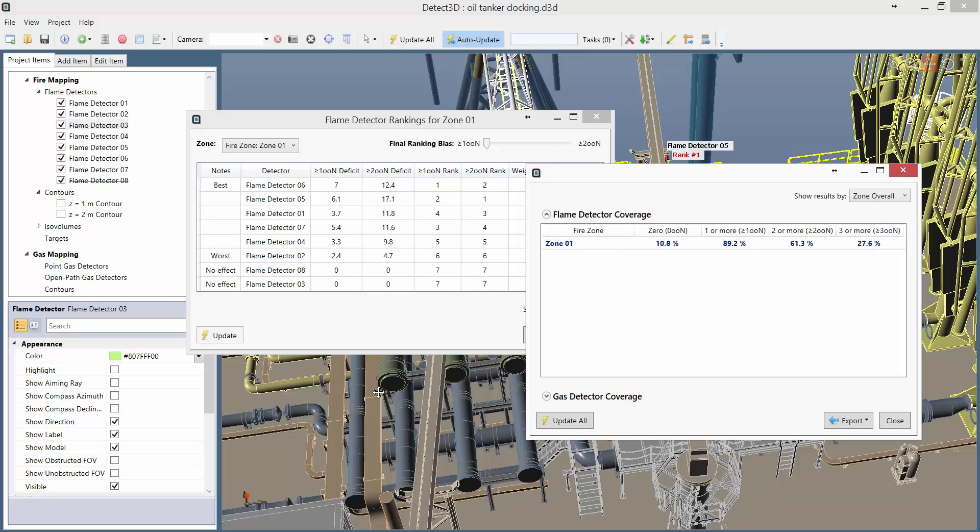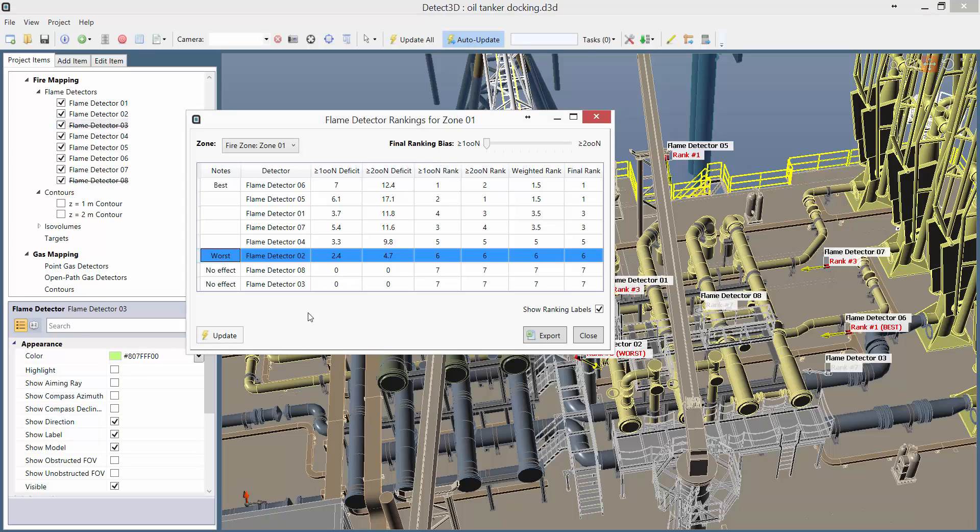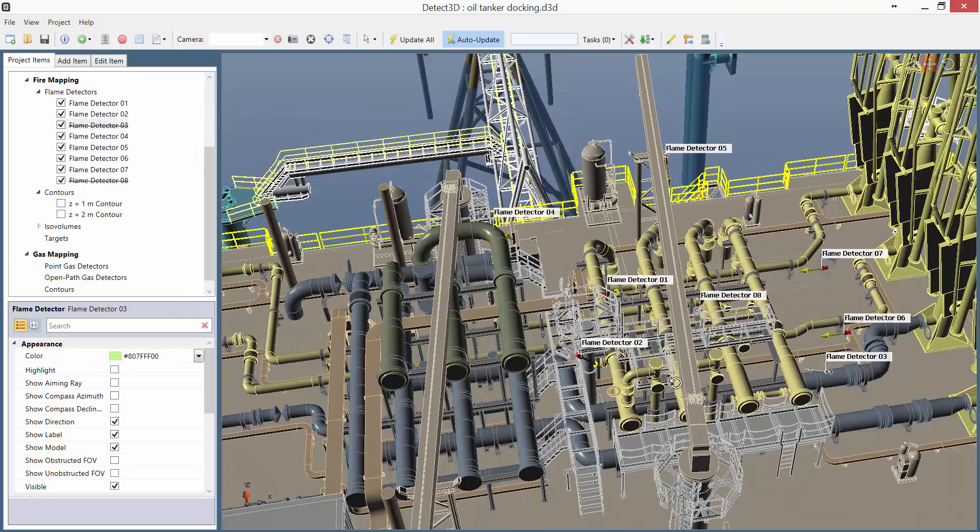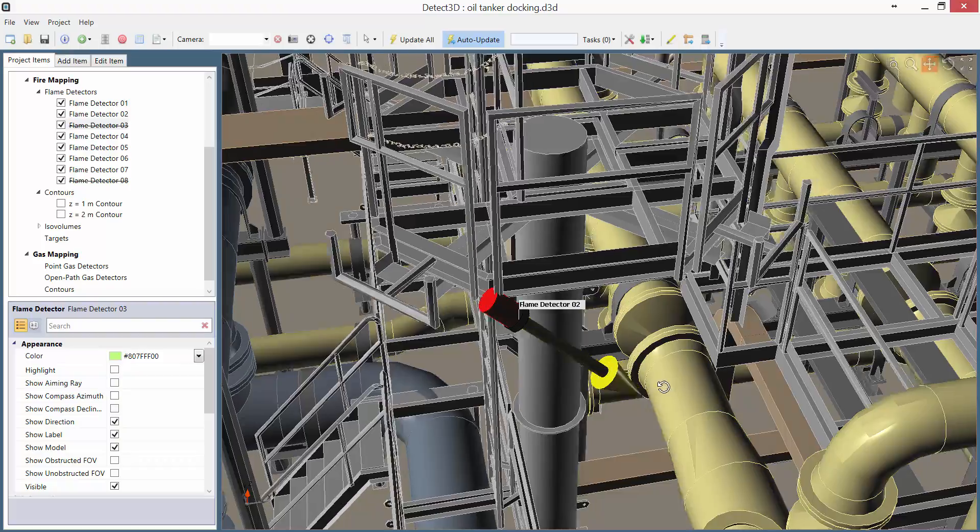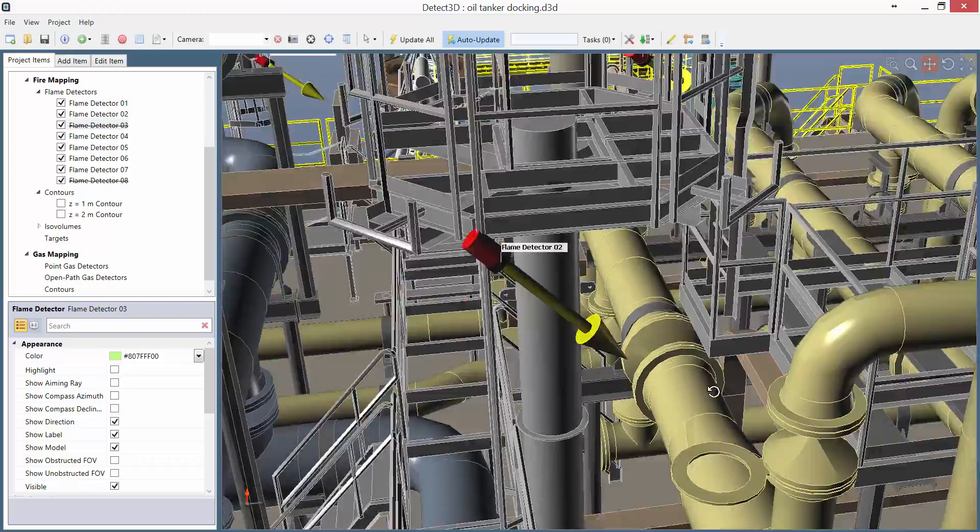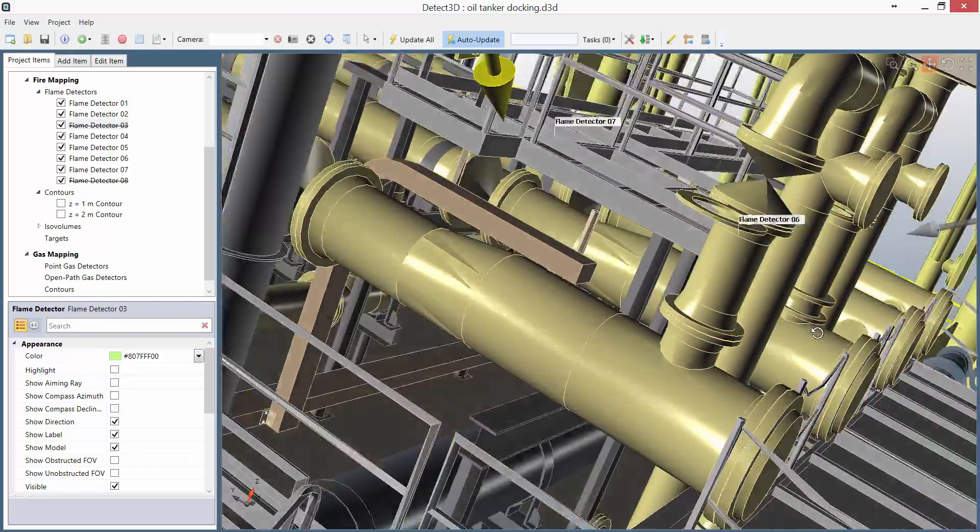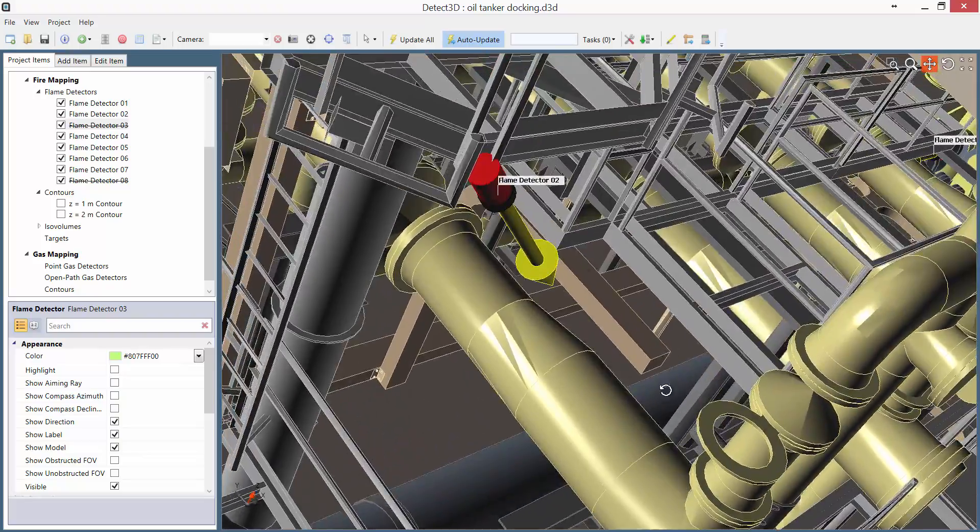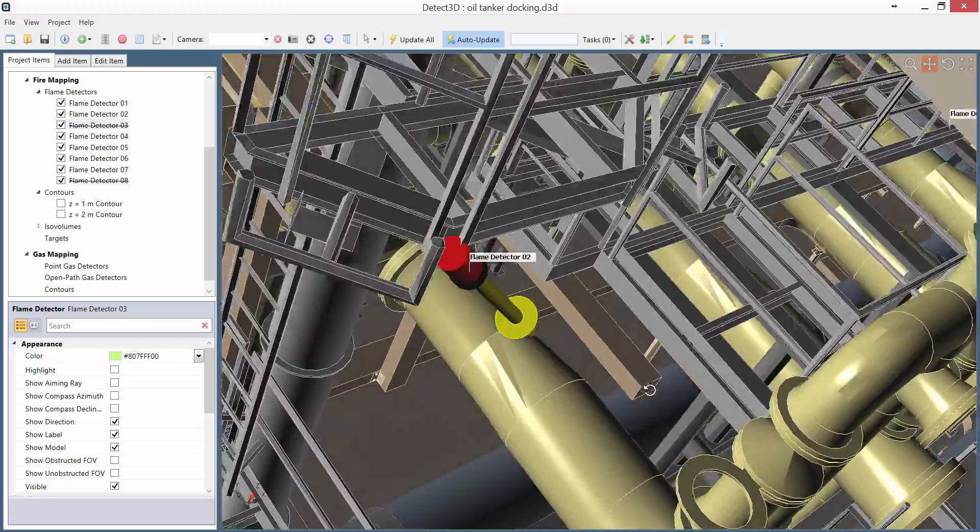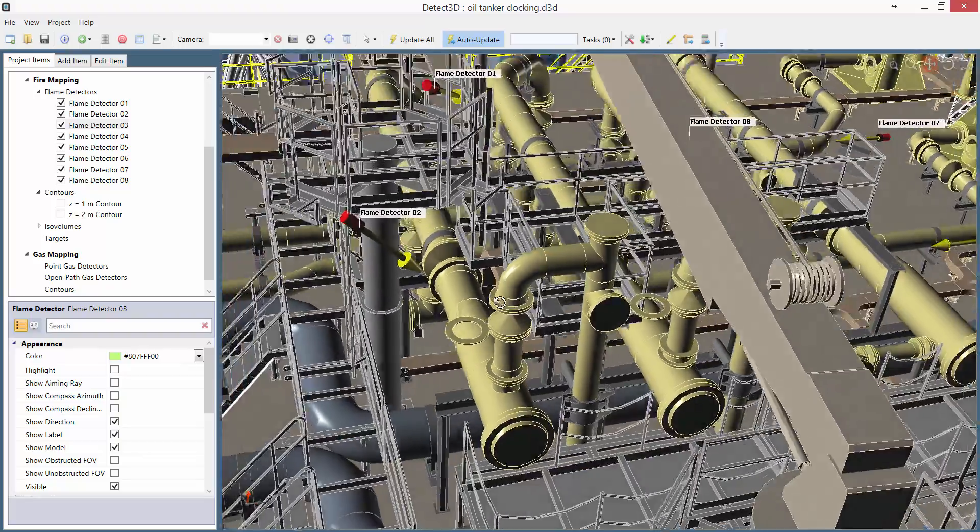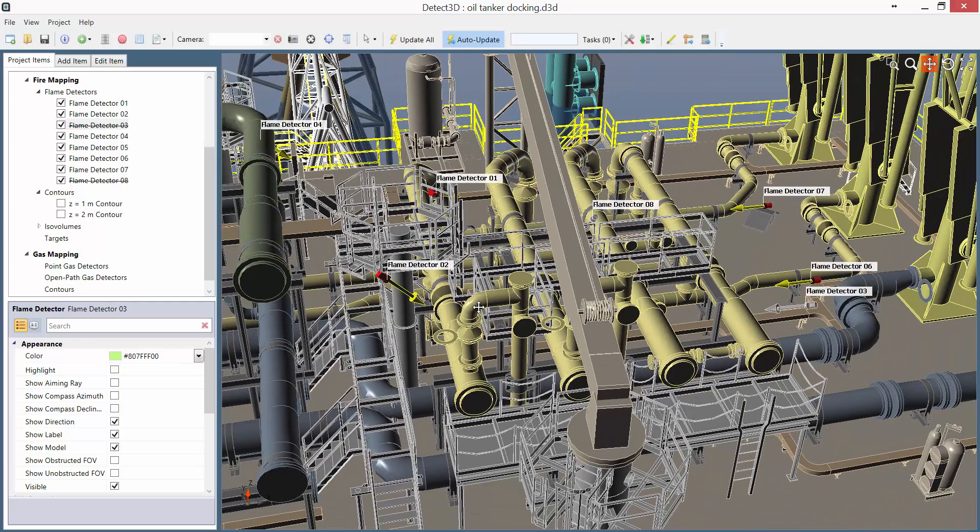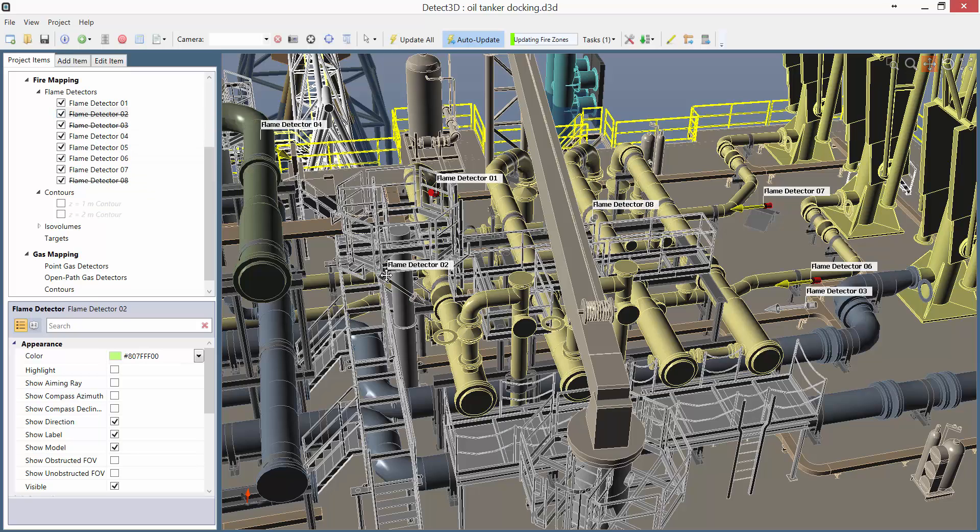Now let's see if we can get the coverage back over 90% by repositioning a detector. The ranking tool says that Detector 02 is now the least effective. Just for a sanity check on that result, we can have a look at Flame Detector 2 in the main window, and here it is. It is looking directly at some pipe work, and also some structure as well. So I'm actually going to go ahead and disable that detector. And instead of moving it, I'm just going to add a new detector in its place.